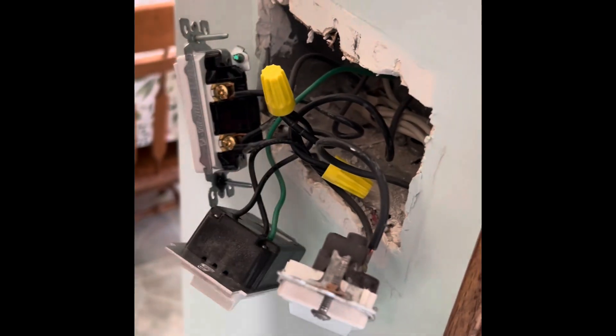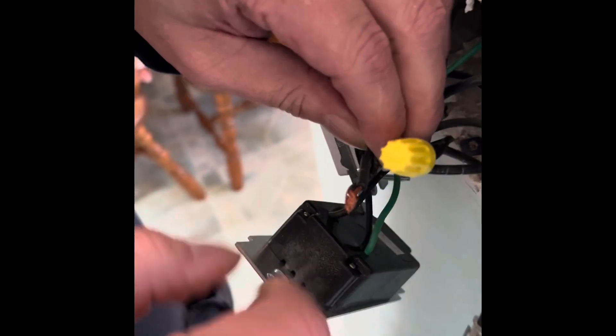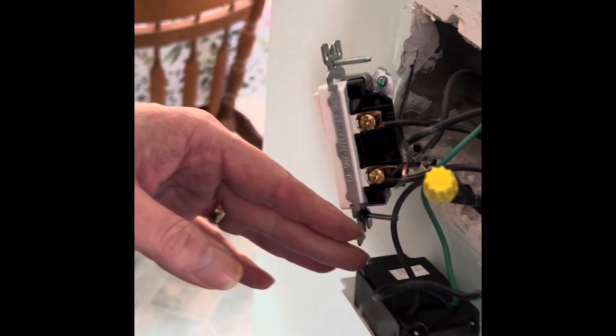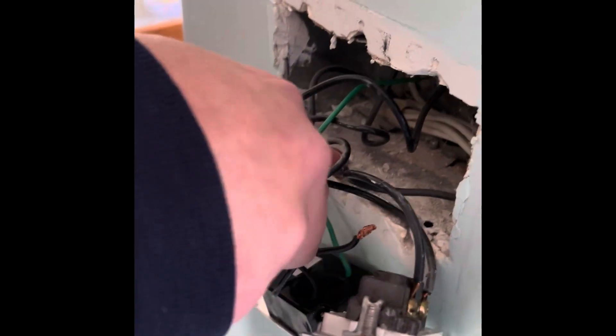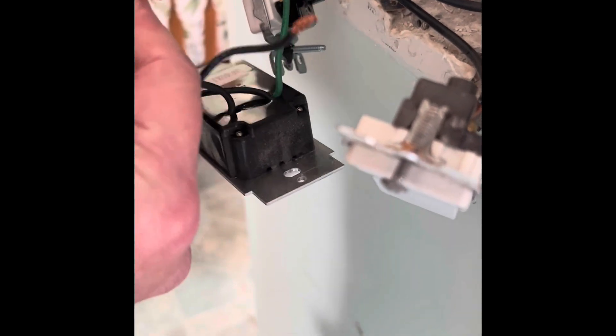This one's a little different because of the Marrette — or wire nut, as some people call it. That one wasn't held on very well. That wire didn't literally break — it just wasn't on very well; this one wasn't in the Marrette properly.